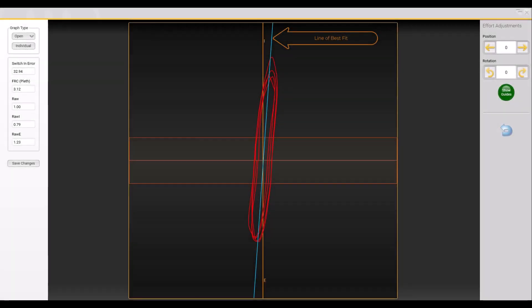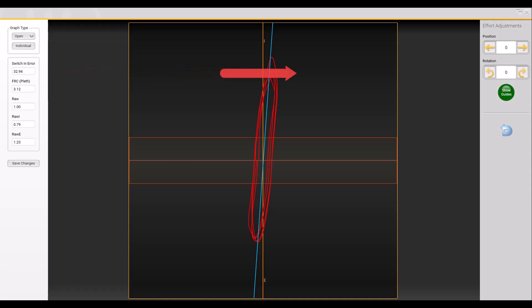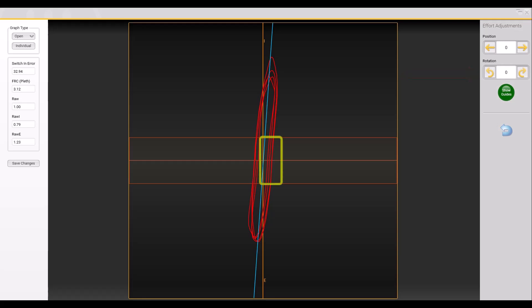To adjust the line of best fit for an airway resistance effort, double-click on the graph. The tracing that will be displayed — open or closed — will be the last trace selected from the previous effort. From Graph Type in the upper left, select Open from the drop-down menu. The red or open shutter panting efforts will be displayed. Use the rotation adjust arrows in the upper right to adjust the angle of the line of best fit if needed. Remember to only use the data between the red flow lines when adjusting.